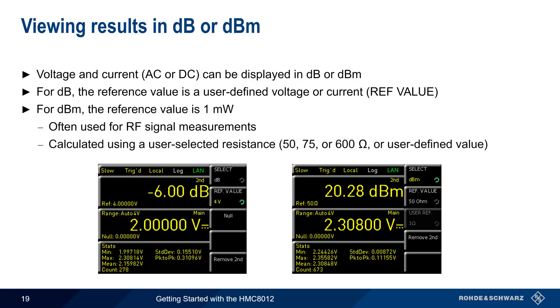One second measurement option for voltage and current is showing values in dB or dBm. If dB is selected, the displayed values are relative to a user-defined voltage or current – for example, with a reference value of 4 volts and a measured value of 2 volts, the difference is minus 6 dB. dBm measurements are always made relative to 1 milliwatt, which is a common measure when working with RF signals. The dBm value is calculated based on a user-selected resistance, with preset values for 50, 75, and 600 ohms, or any arbitrary value can be manually entered.